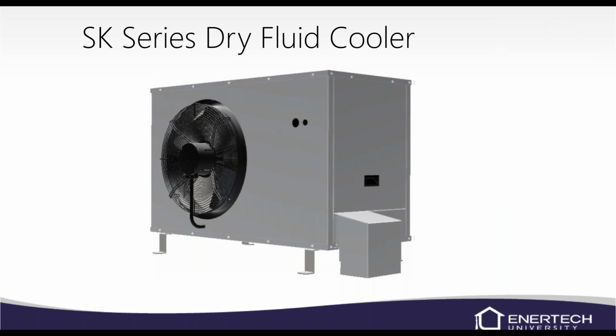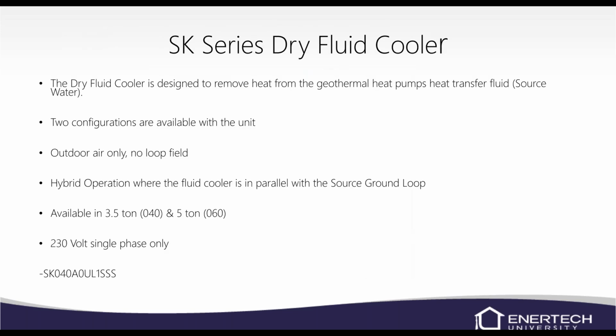This is the SK series dry fluid cooler. It kind of looks like a condenser unit. It does have an ECM fan on it, a little pipe shield off to the lower right there, and then the access door right above it. On the other side, there's a vertical coil. So again, kind of looks like a condenser unit. It's designed to remove heat from the geothermal heat pump fluid, so like the source water.